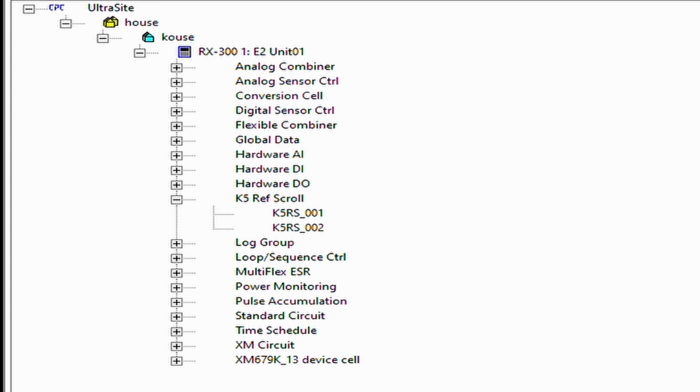I don't have a suction group programmed here, but you could drop down and choose your suction group. You tell it what compressor it is. If it's compressor 1, it's compressor 1. If there's an unloader, obviously on a K5 scroll you won't have this, but on a CoreSense module, this matters. So if compressor 1 has an unloader on it, the next compressor is going to be compressor 3, not compressor 2, because it spaces them out via the suction group. So output 2 is going to be your unloader for compressor 1. So you always want to skip it and make it that.